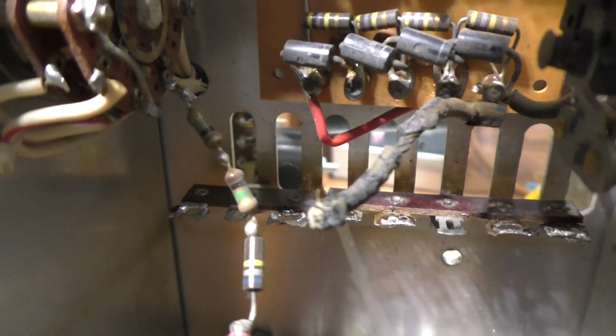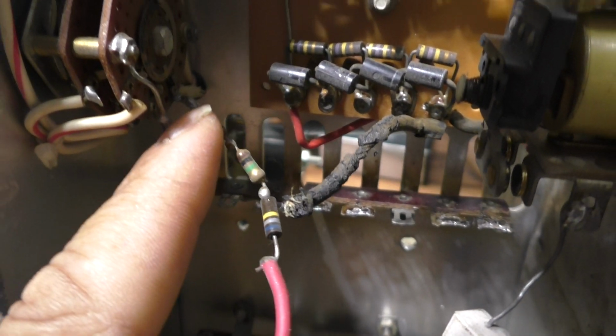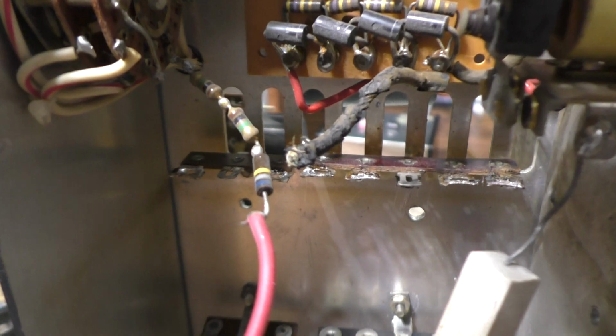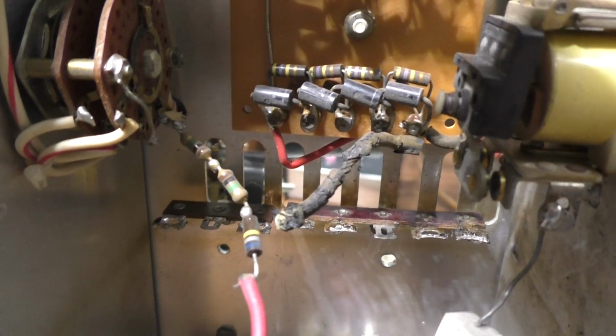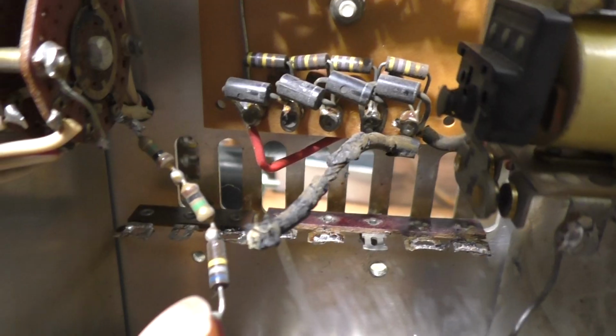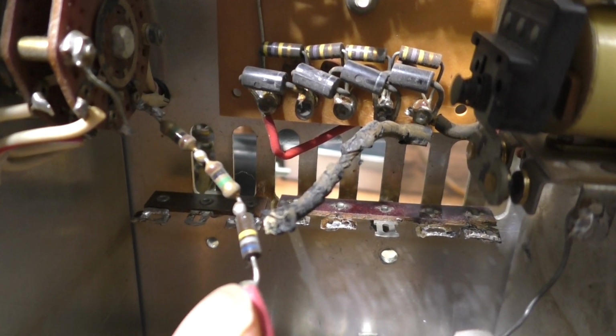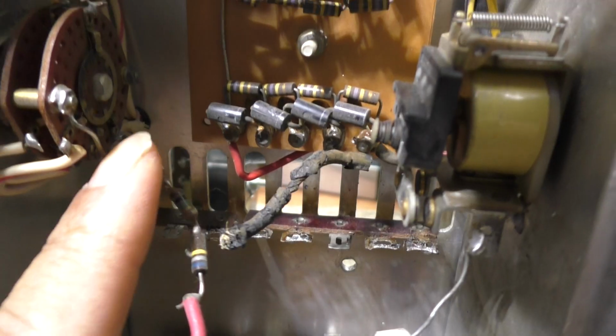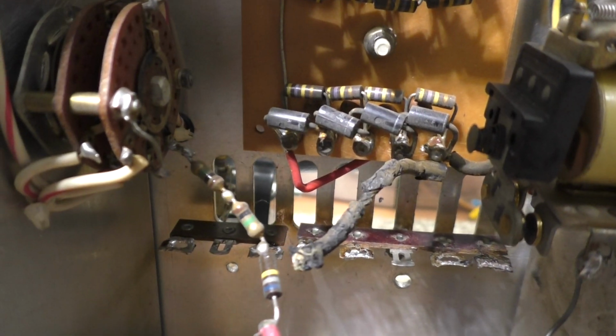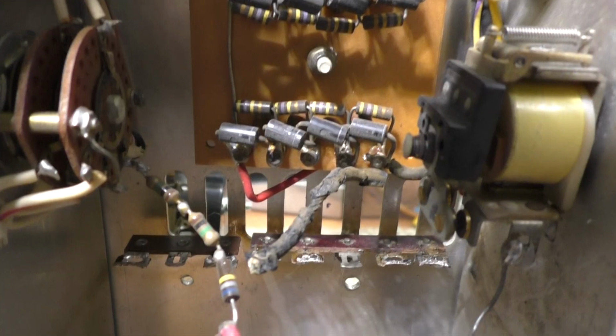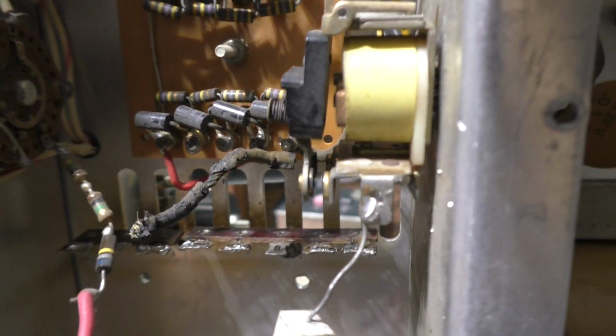For the voltage reading on the multimeter, it uses dropping resistors across the high voltage. This connects directly to the high voltage, and these resistors are high impedance, high reading resistors that drop that high voltage - from 2500 or 2700 volts, whatever this runs on - down to about 1 volt, which is what feeds the meter, since most mechanical meters run on about 1 volt.